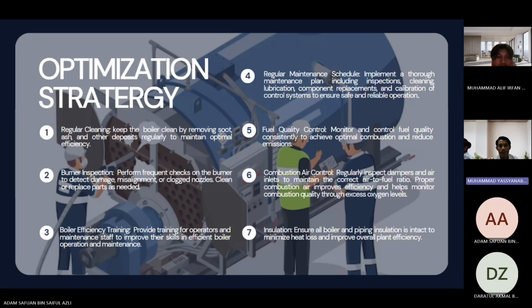Optimization strategy. First, regular cleaning. Keep the boiler clean and remove soot and other deposits regularly to maintain optimal efficiency. Next, burner inspection. Perform frequent checks on the burner to detect damage, misalignment, or nozzle problems. Clean or replace parts as needed. Third, boiler efficiency training. Provide training for operators and maintenance staff to improve their skills in efficient boiler operation and maintenance.